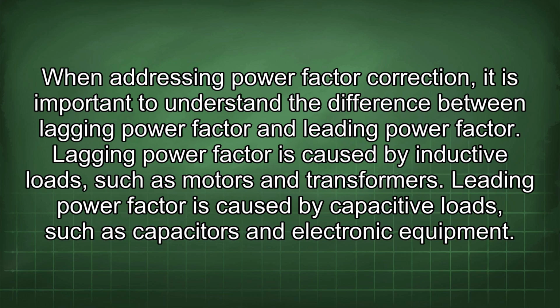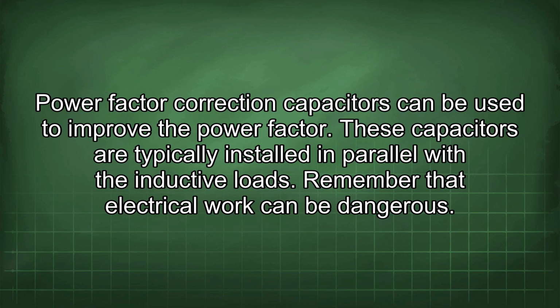When addressing power factor correction, it is important to understand the difference between lagging power factor and leading power factor. Lagging power factor is caused by inductive loads such as motors and transformers. Leading power factor is caused by capacitive loads such as capacitors and electronic equipment. Power factor correction capacitors can be used to improve the power factor. These capacitors are typically installed in parallel with the inductive loads.